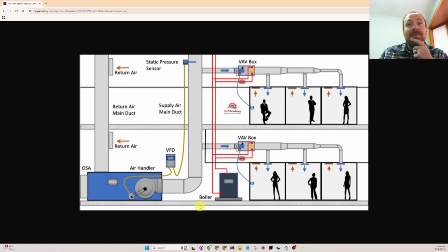So just a little bit about the theory behind what I'm trying to do. When we're looking at Guideline 36 energy efficiency concepts for an air handling unit, a variable volume air handling unit that serves VAV boxes, there's a variable fan right here on the air handling unit that's on a VFD with a static pressure sensor. There would also be a leaving air temperature sensor, and when we are doing concept algorithms, like filtering values, maximum values in an array of data, what I'm referring to is zone level data.